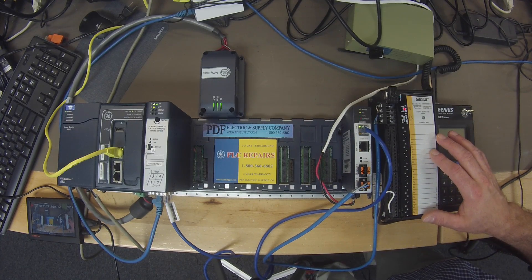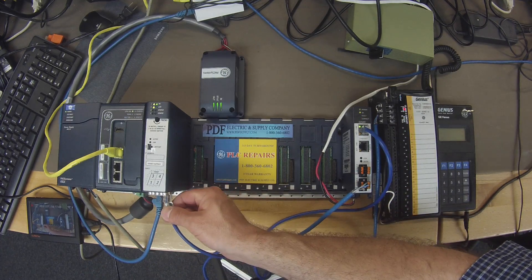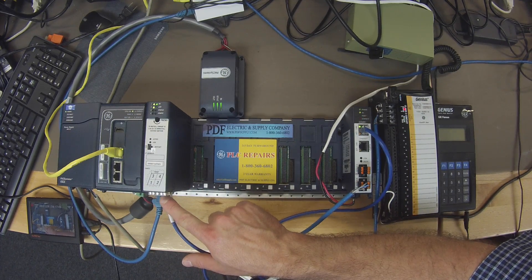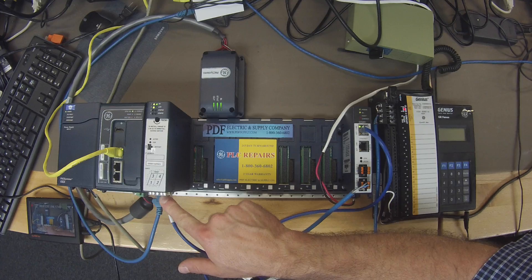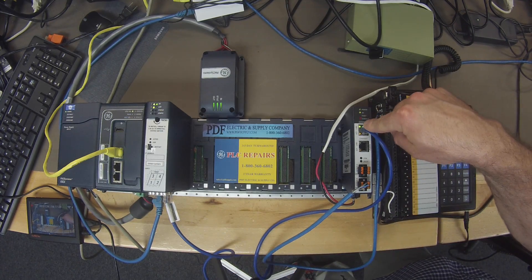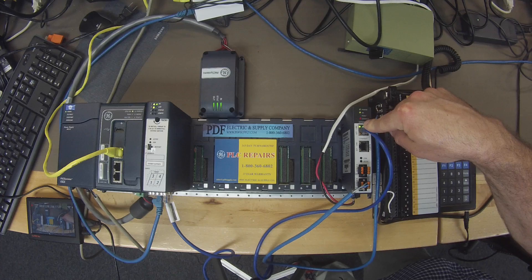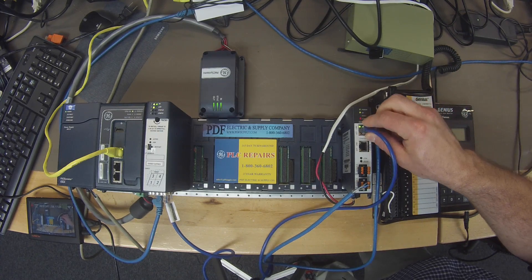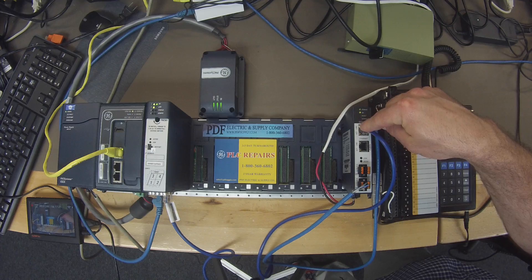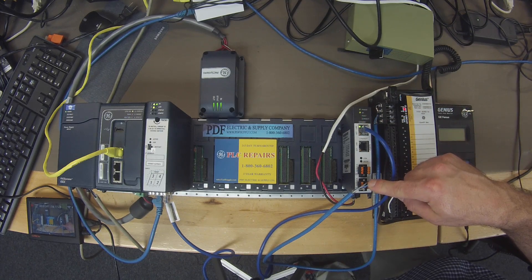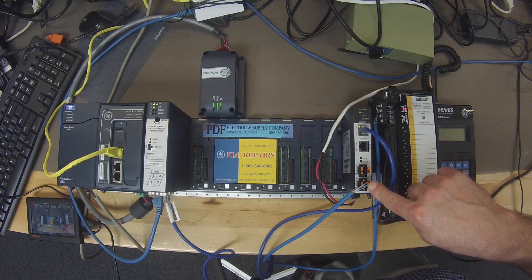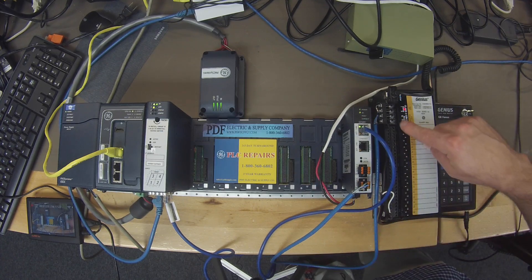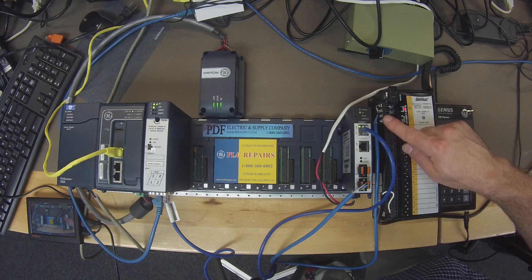A couple of things that I wanted to point out. I have a straight Ethernet cable that's going directly from my PNC001 PROFINET controller to the GCG001. The point I'm trying to make here is that it's not a crossover cable, it's just a straight Ethernet cable going directly in port 1, and out of serial B, I have a serial cable going to the serial port on my Genius Block.